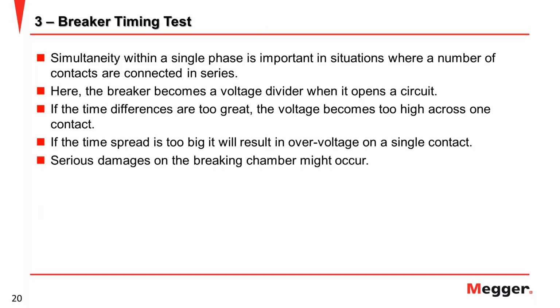Next test, breaker timing test. Breaker timing test is also part of the basic test. We need to test this to verify the operating time of the breaker, to avoid the condition becoming a voltage divider when the breaker is operated, especially for a breaker that has two interrupters per phase. Most standards state the difference between three phases should be less than 2 milliseconds. So you need to verify your breaker follows that standard.